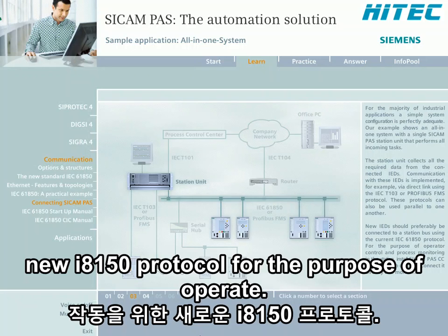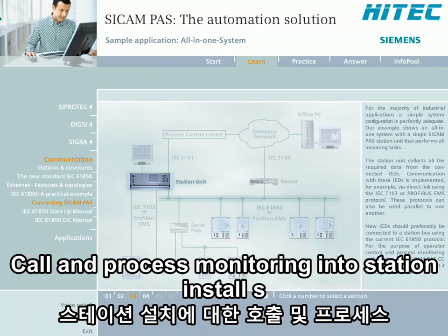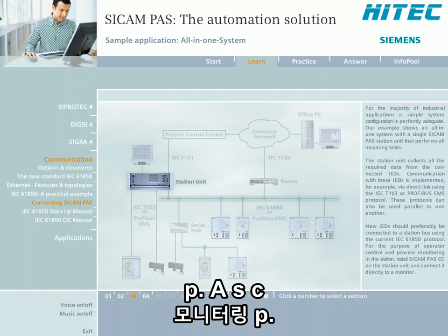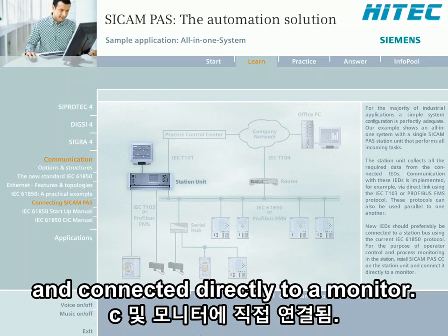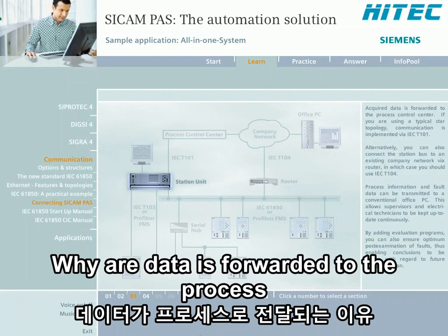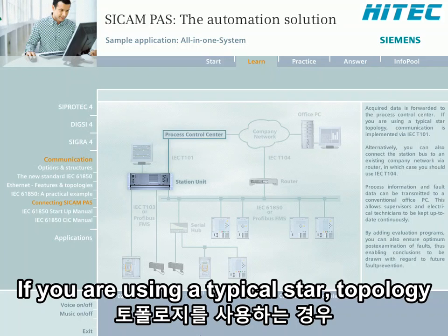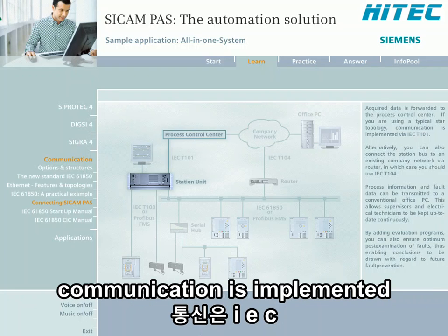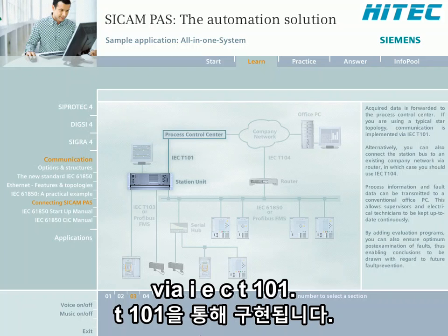New IEDs should preferably be connected to a station bus using the current IEC 61850 protocol. For the purpose of operator control and process monitoring in the station, install SICAM PAS-CC on the station unit and connect it directly to a monitor. Acquired data is forwarded to the process control center. If you are using a typical star topology, communication is implemented via IEC T101.